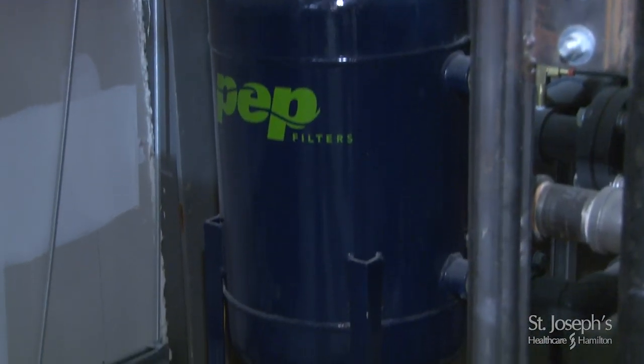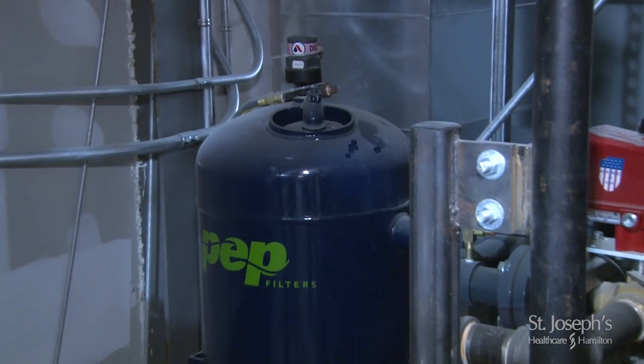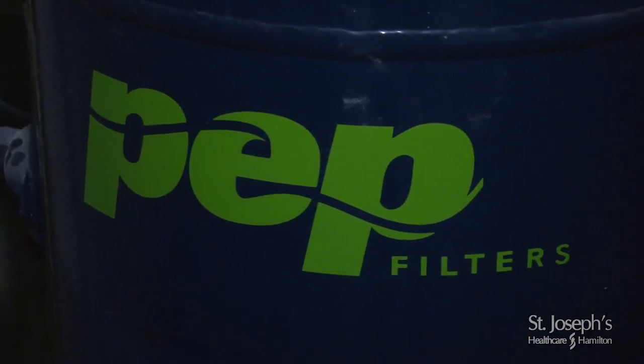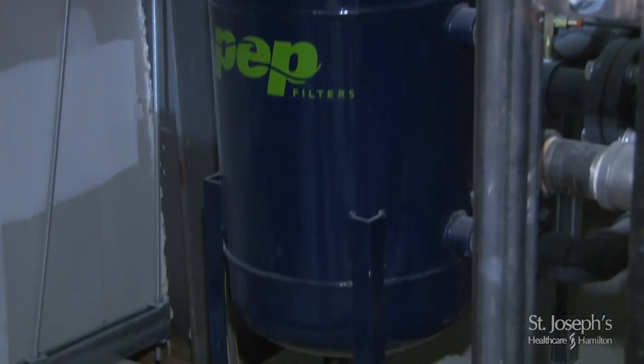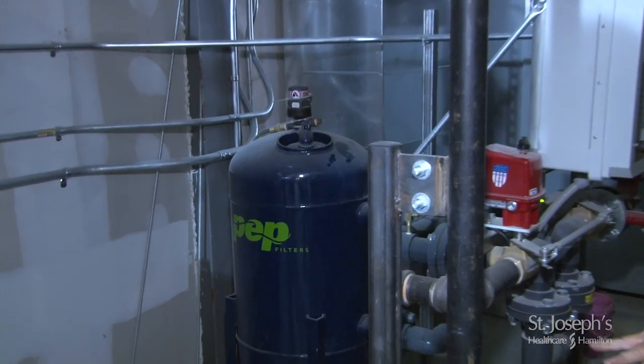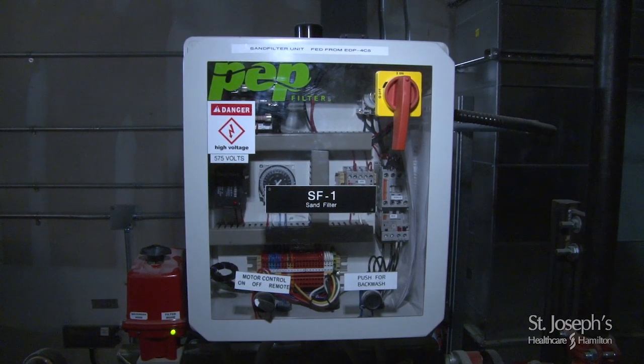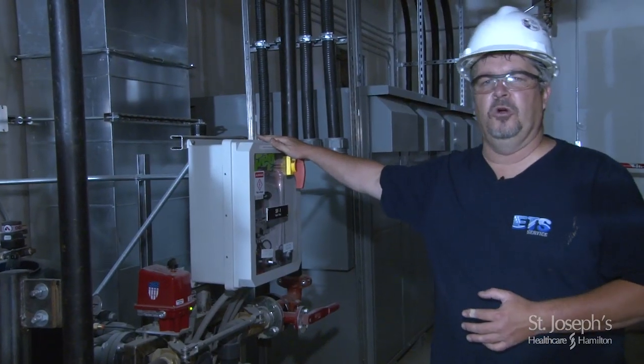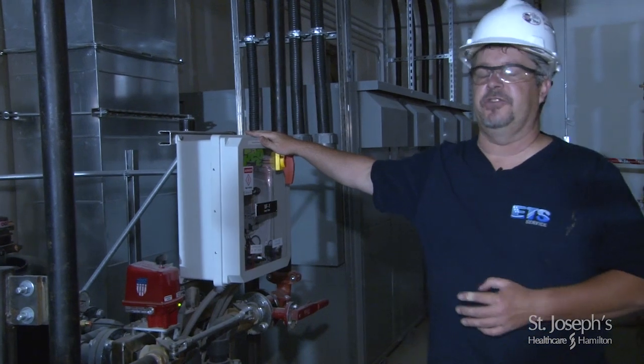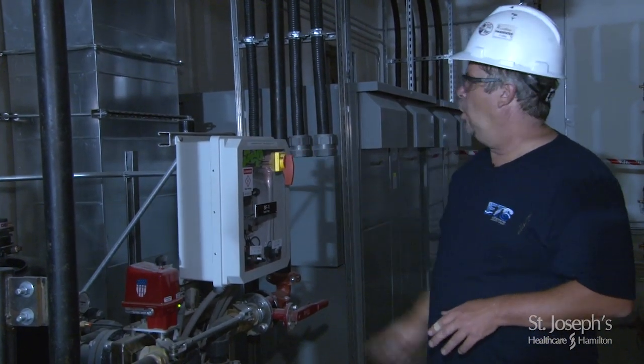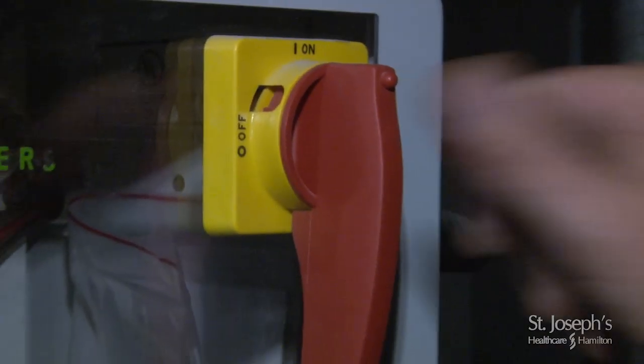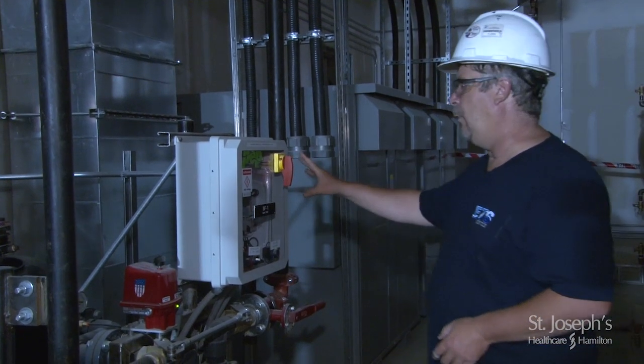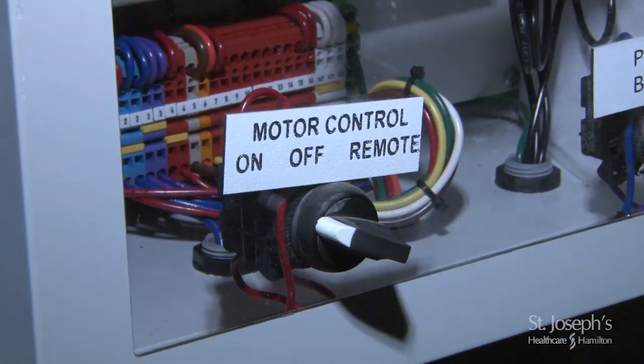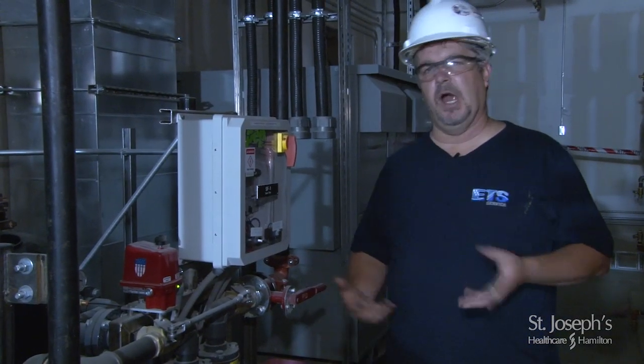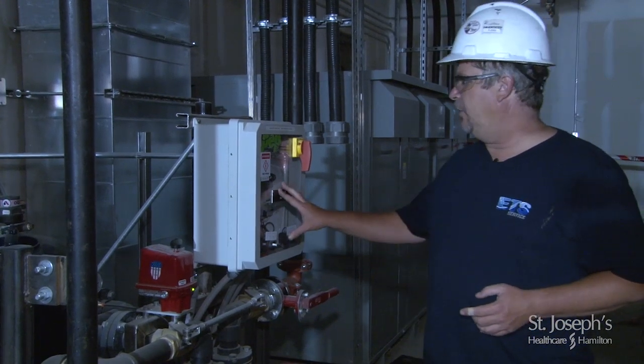Inside this tank is a series of very small pebbles to start at the bottom, up through sand media sitting on top of those pebbles. The water flows through that media and then back out of the filter, allowing it to trap any small particles, anything that might have come through from the cooling tower. This unit is fully automatic. Although we have a control panel on the front, that is all programmed at the factory, and there are actually no serviceable items inside this control panel. The only thing the operator needs to be concerned with is that the power switch is in the on position so that we know that we have power, and then down here we have the motor in the on position as well. That means the filter is running, it's doing its job, and there's not much more you can do with this.